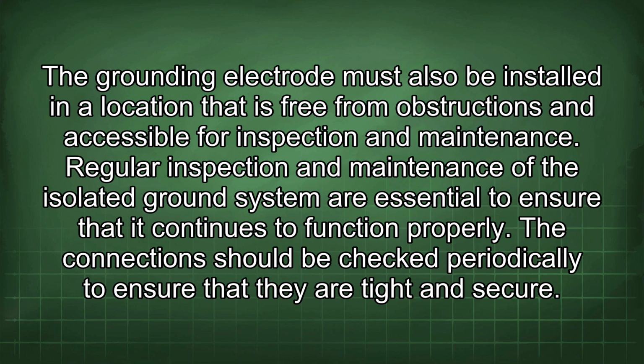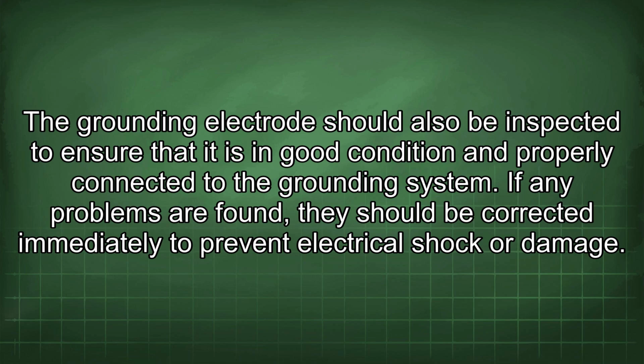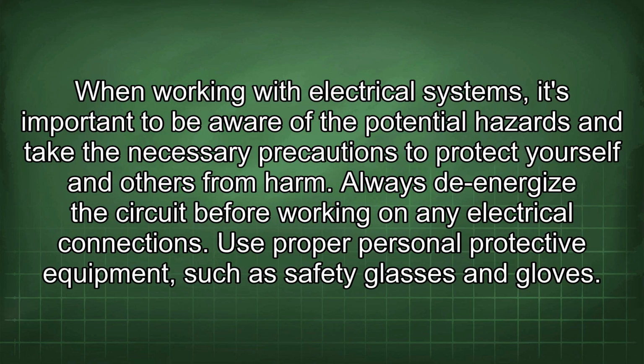Regular inspection and maintenance of the isolated ground system are essential to ensure that it continues to function properly. The connections should be checked periodically to ensure that they are tight and secure. The grounding electrode should also be inspected to ensure that it is in good condition and properly connected to the grounding system. If any problems are found, they should be corrected immediately to prevent electrical shock or damage. When working with electrical systems, it's important to be aware of the potential hazards and take the necessary precautions to protect yourself and others from harm.